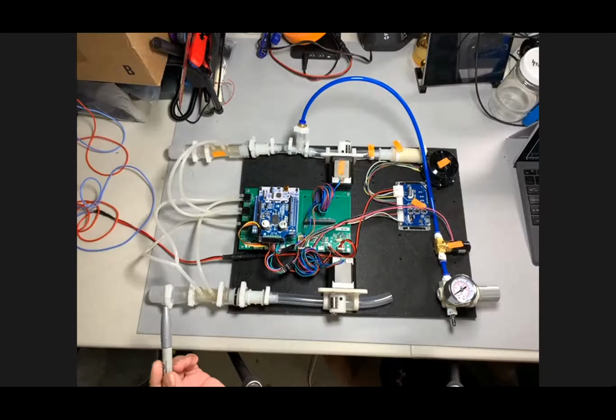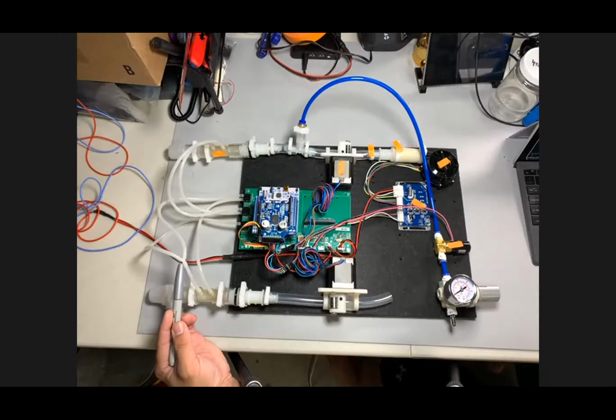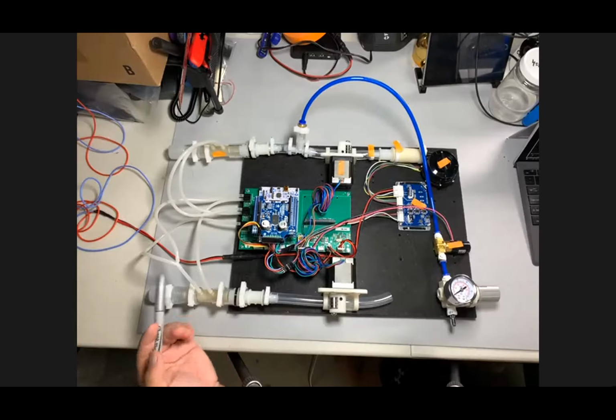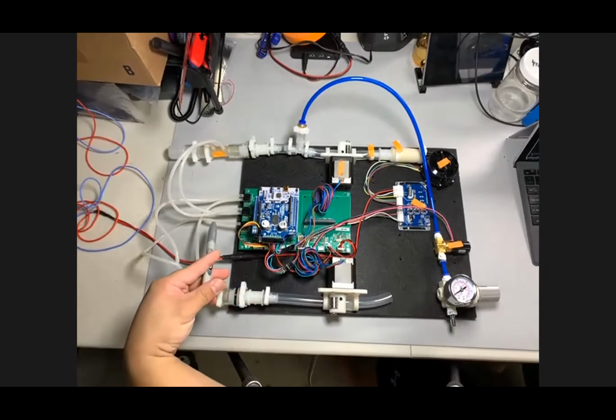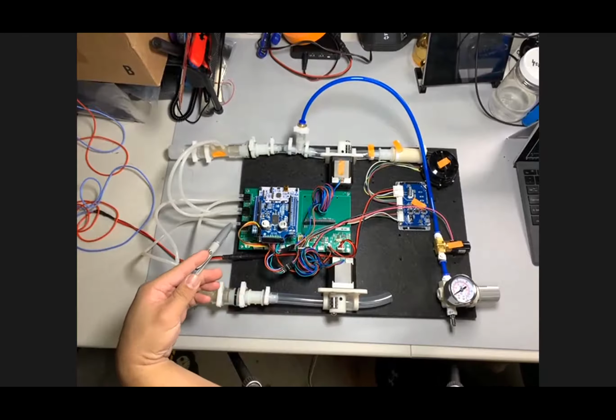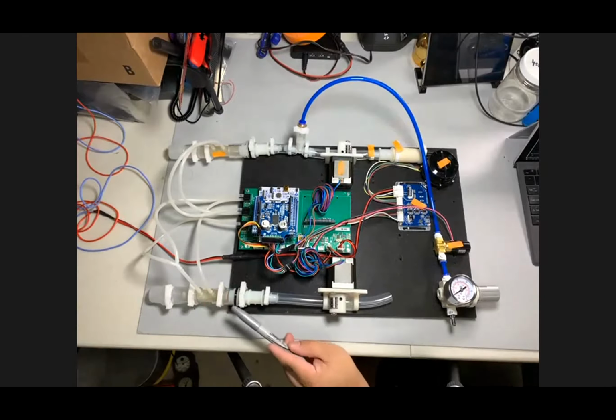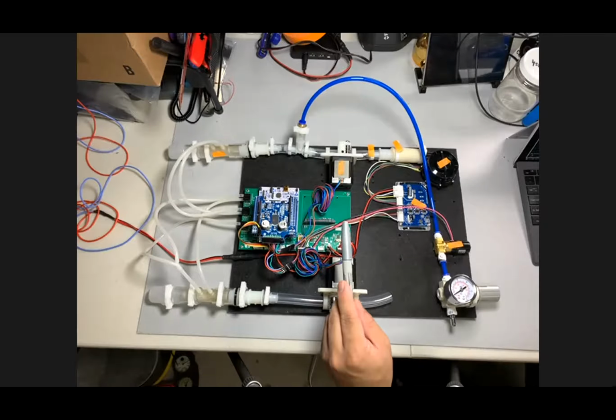And one difference here is that we also tap off the patient pressure sensor. So in the exhale limb, we will measure the pressure that we're delivering to the patient as well. So there's a Y here, which then goes to the patient pressure sensor, which is here on the circuit board. Exiting the venturi, downstream of the venturi, we have another adapter, which brings us back to this 3/8 inner diameter tubing, which allows us to go through the exhale pinch valve. This is the same pinch valve. It's exactly the same design as the one in the inhale leg.